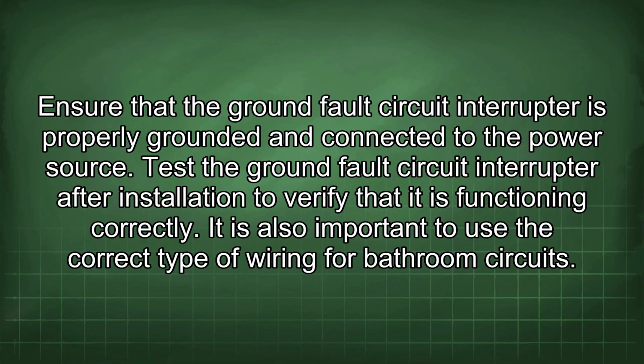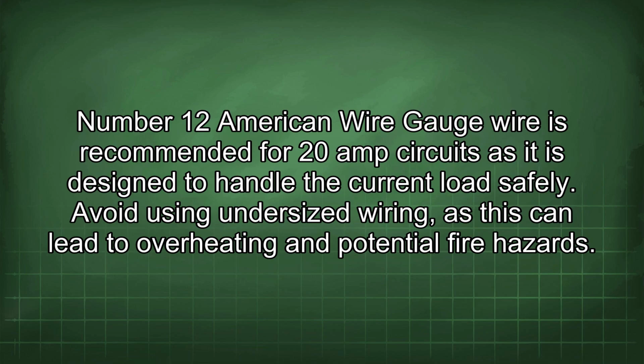It is also important to use the correct type of wiring for bathroom circuits. Number 12 American wire gauge wire is recommended for 20 amp circuits as it is designed to handle the current load safely. Avoid using undersized wiring, as this can lead to overheating and potential fire hazards.